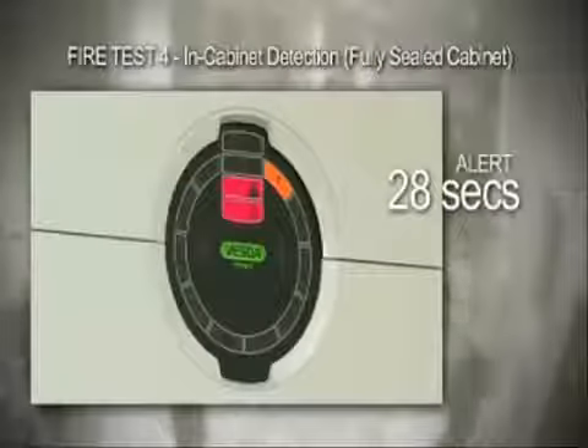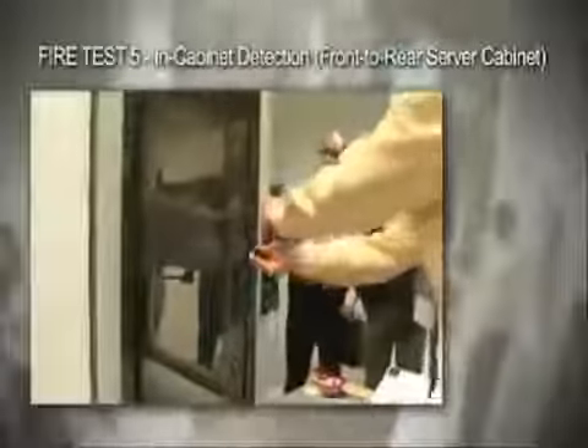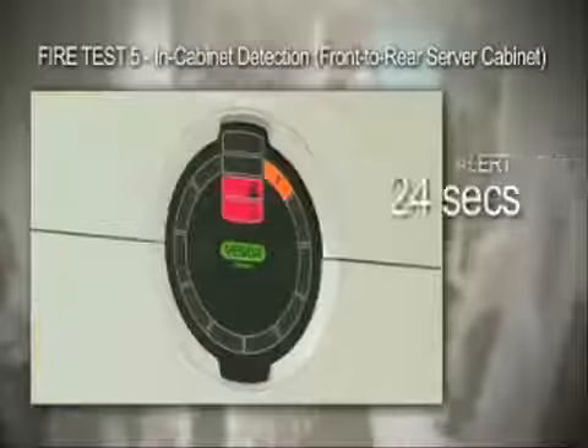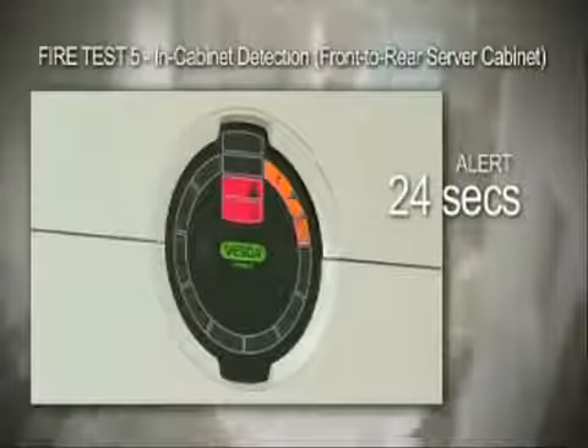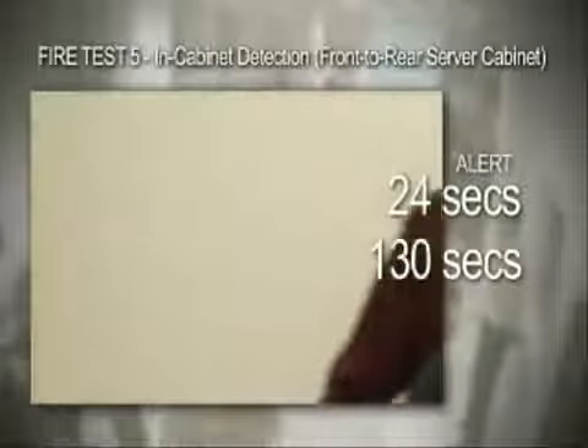In this test, the server cabinet is fully sealed and the sampling pipe is located within the top of the cabinet. At 28 seconds, the VESDA Laser Focus, sampling from within the cabinet, goes into alert. The VESDA sampling pipe is located at the back of the server cabinet to catch the smoke as it is carried with air currents. At 24 seconds, the VESDA Laser Focus detector goes into alert. After 130 seconds, none of the other detectors had detected the smoke.